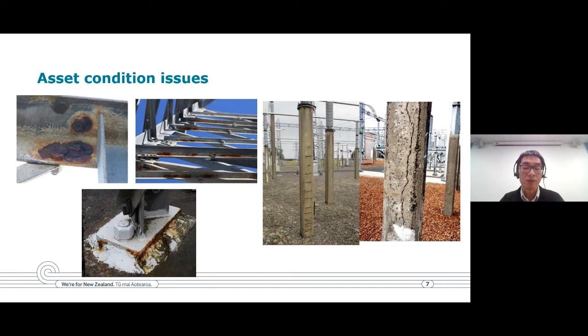Typical condition issues for steel lattice gantries, both 110 kV and 220 kV, include localized corrosion under the armpit of angle steel, which is pretty common, and corrosion underneath the base plate and the grout. With concrete support posts, used a lot for 220 kV rigid bus bars, some sites start seeing spalling of concrete over the secondary reinforcing, and more concerning, major cracks alongside the main reinforcing bars.